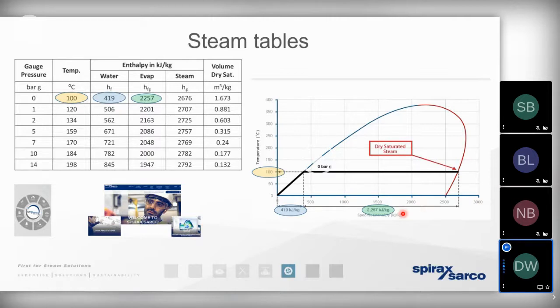The problems we encounter by leaving that condensate there: it means we need to install a greater number of steam traps to remove that condensate. If we don't, we're more susceptible to erosion, corrosion, and water hammer. It also means that any dry steam will degrade as it passes across that trapped mass of condensate, meaning that not only do we get a reduced mass of steam finding its way to the process, but the steam that does find its way to the process will have less energy contained within it. So wet steam is going to bring a greater heat loss and more condensate, not only at the process, but especially in the distribution pipework.